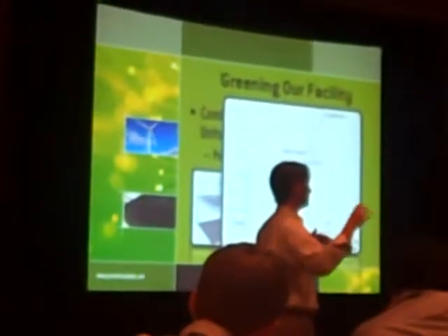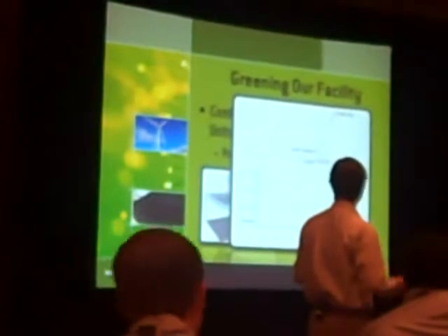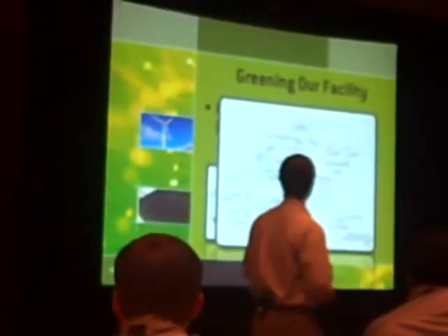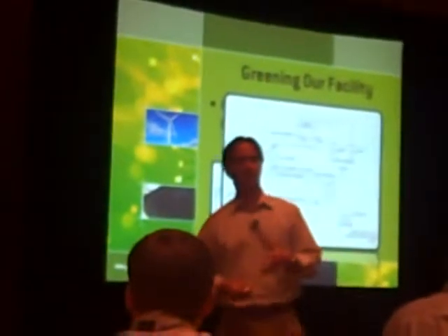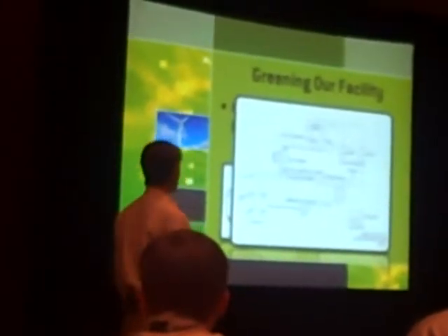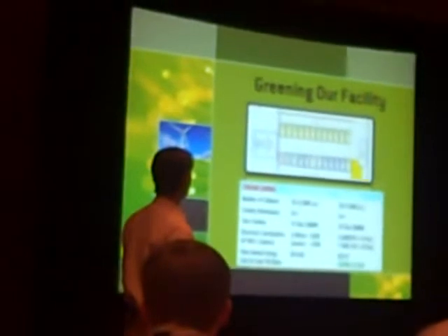And then we can basically manage any kind of combination in between the utilization of the CRAC unit and the outside ambient air temperature. The fortunate thing is, again, at the hottest day, we still don't need to use the CRAC unit in condenser mode. It's there. It can be used, but we don't have to turn it on. So we have a semi-sophisticated PLC that manages all this, measuring outside ambient air temperature, inside temperature, measures the differential pressure, measures the humidity inside and out, and then controls the whole combination of CRAC unit and economizer.